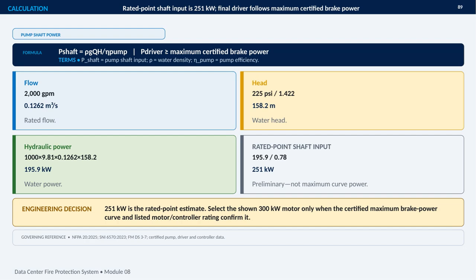The rated flow is 2,000 gallons per minute, converted to 0.1262 cubic meters per second. The corresponding head is 225 psi, or 158.2 meters of water head. Using water density, gravity, flow, and head, the calculated hydraulic power is 195.9 kilowatts. To account for pump efficiency, the hydraulic power is divided by the stated efficiency of 0.78. That produces a rated point shaft input of approximately 251 kilowatts.